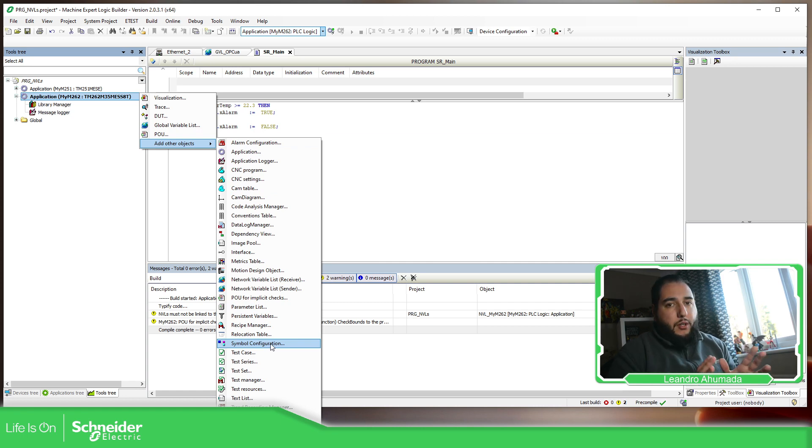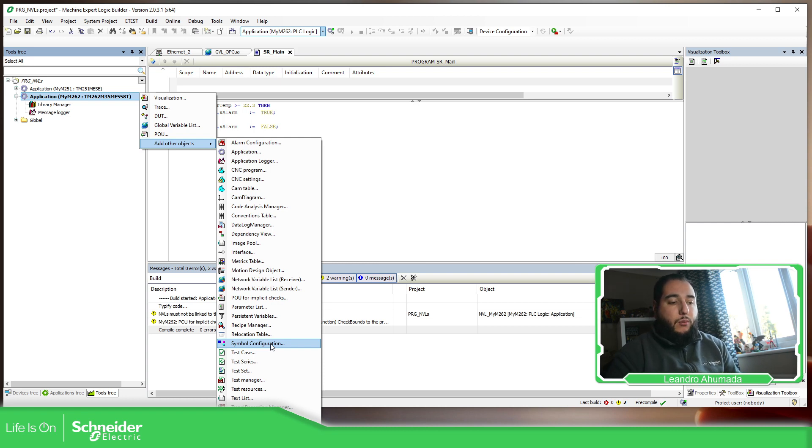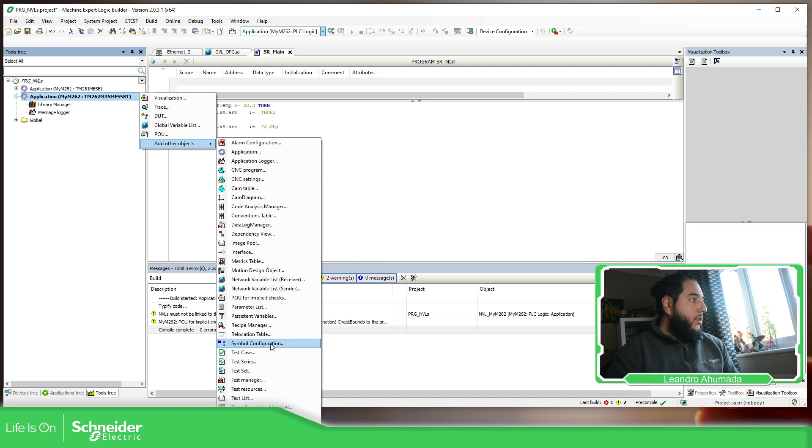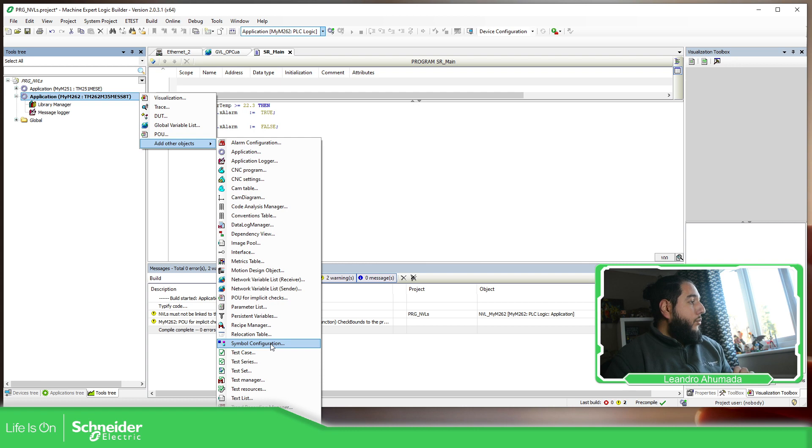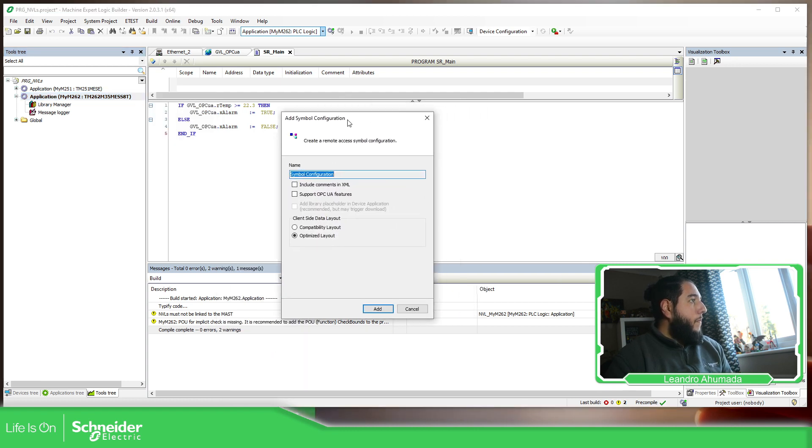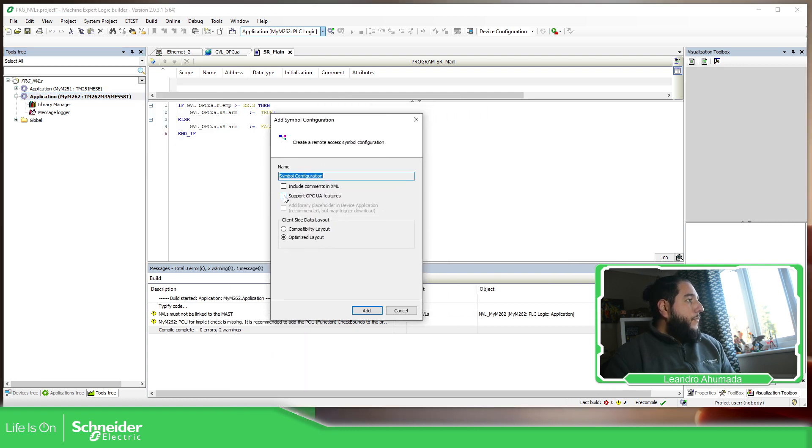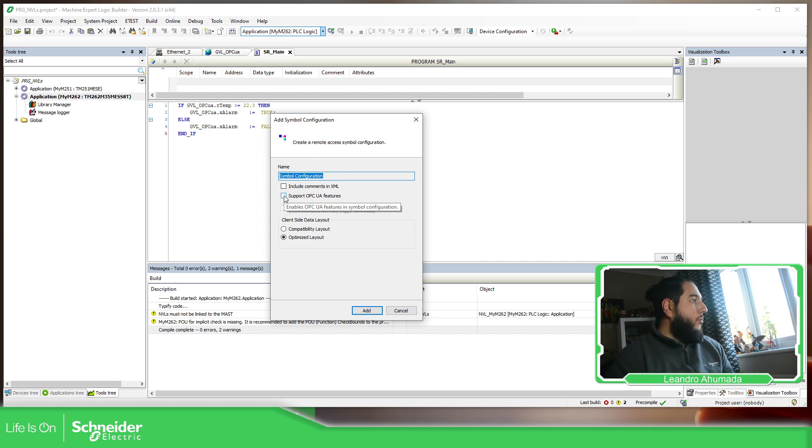This part is a little bit different compared to the Modicon M241 and M251 that we need to add a specific OPC UA symbol configuration. But this one is the same. We just need to use the symbol configuration. As soon as we press symbol configuration, here we have the possibility to enable the OPC features. So we just need to click on support and then add.